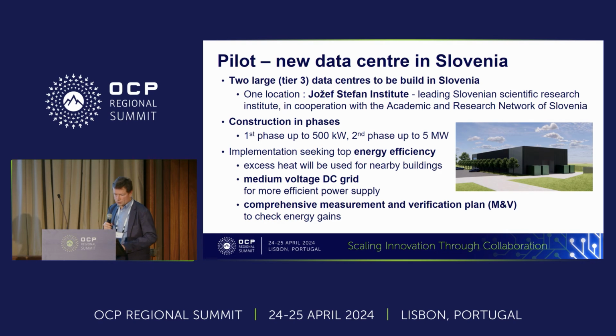It will be done by Jožef Stefan Institute, and they preview 2 phases. In the first phase, they will do 500 kilowatts. In the next phase, they go up to 5 megawatts. There will be a lot of high-performance computing in this data center. The excess heat they want to use directly by the nearby buildings, and this medium voltage DC grid will be implemented in this data center. In order to check the gains which we are claiming, a comprehensive measurement and verification plan will be set up.